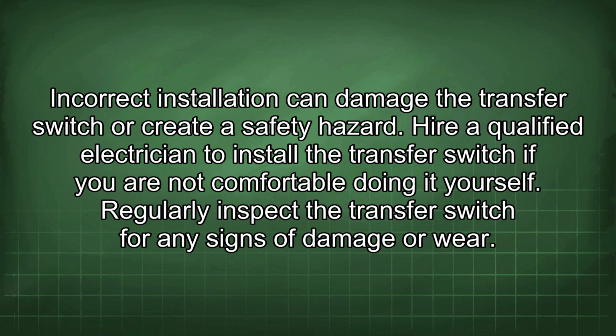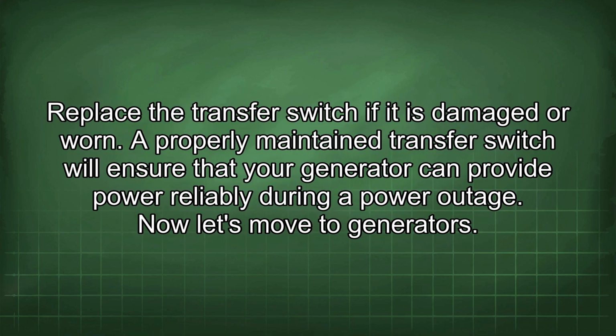Regularly inspect the transfer switch for any signs of damage or wear. Replace the transfer switch if it is damaged or worn. A properly maintained transfer switch will ensure that your generator can provide power reliably during a power outage.